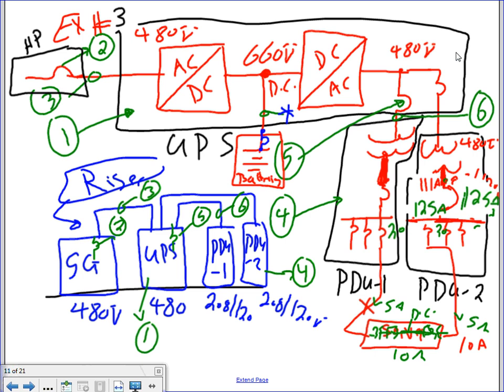From here, they have two PDUs. They take one branch circuit from this one and one from the other one, and they feed it to a computer server. That's how your server is. So literally, they take a 20 amp circuit breaker, and a 20 amp circuit breaker underground, underfloor, to a receptacle like this. So they will have two receptacles, one coming from one panel, one from the other panel, and my computer has two cords. One cord will plug in this circuit, and the other cord will plug in the other circuit. So they have dual corded. They have computers, or servers, with two cords on them.